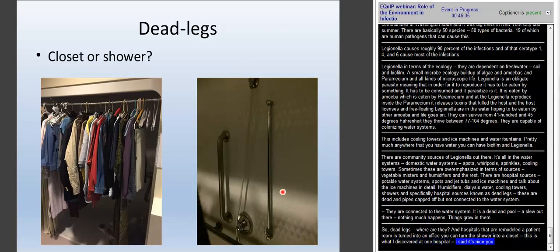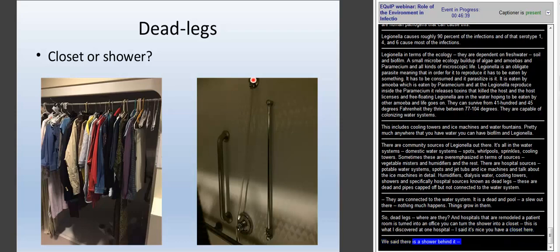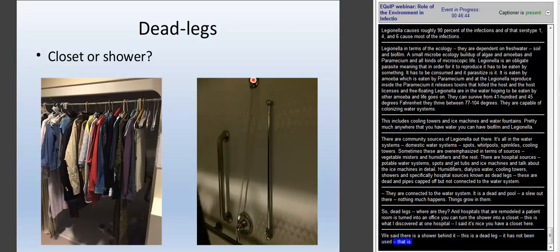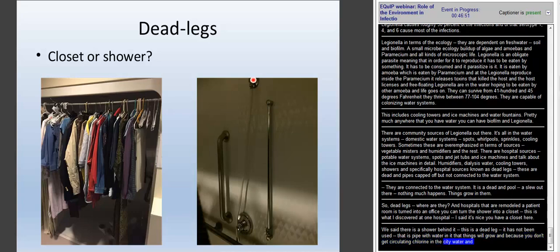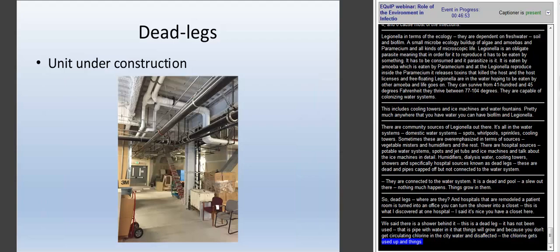This hadn't been used for 5 or 6 years, and that is a bit of pipe that has water in it that things will grow in, simply because you don't get circulating chlorine from the city water to disinfect. The chlorine gets all used up, and then things can grow, and that can be a source of Legionella.